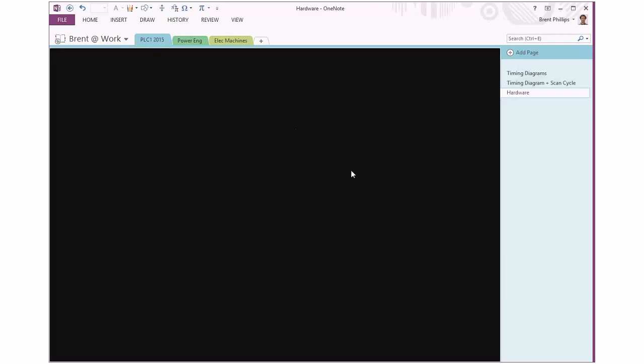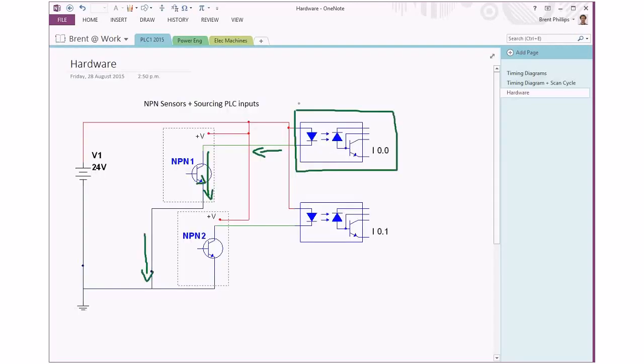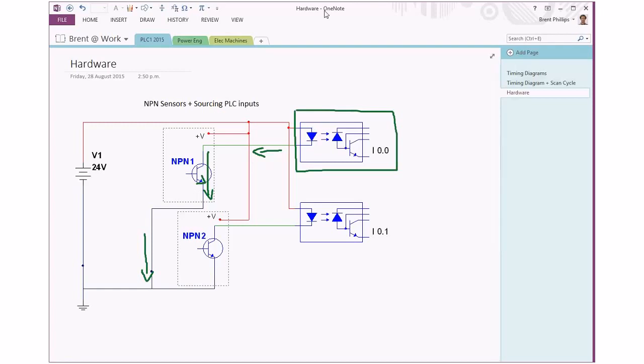This here is our optocoupler which is inside the PLC. That's there for protecting the PLC's sensitive circuits from any voltages or spikes or surges that are out in the outside world. When this transistor in our sensor is turned on, we're getting current flowing through the LED in the optocoupler, and the flow of that current is going to be activating the rest of the circuits inside the PLC and turning on the memory that's associated with that particular wire.